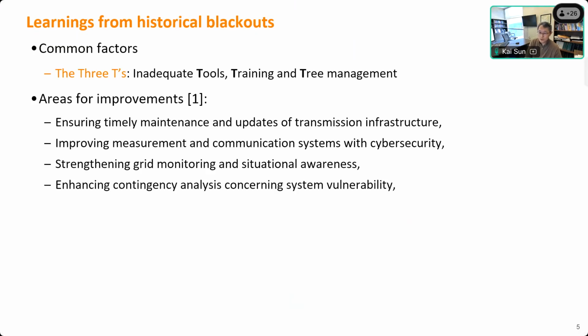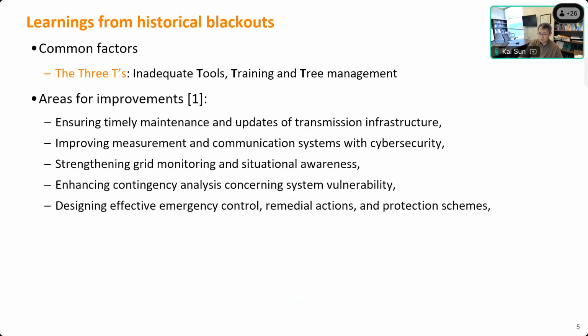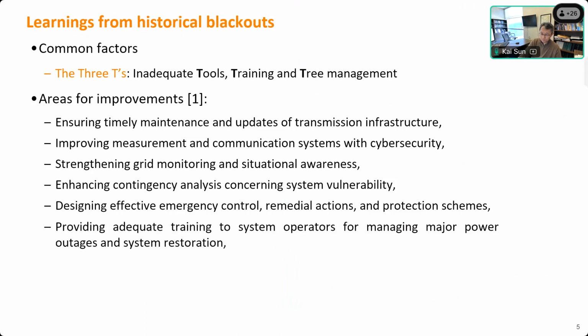Next is to enhance contingency analysis, addressing potential system vulnerabilities through analysis. We also need to design effective emergency control, remediation, or protection schemes, especially wide area control strategies, because cascading failure isn't just a single or double event—it can spread and propagate to a wider area. You need to be prepared at the system level, not just the local equipment level.